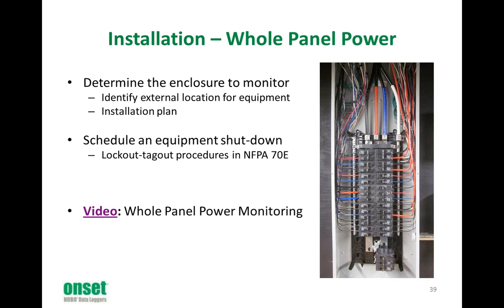So to do whole panel power, you must first determine the enclosure to monitor, identify an external location for the equipment, and come up with an installation plan. For this type of installation, you're going to need to schedule an equipment shutdown and also follow the lockout-tagout procedures in NFPA 70E. We'll now watch a video on how to do this permanent installation.